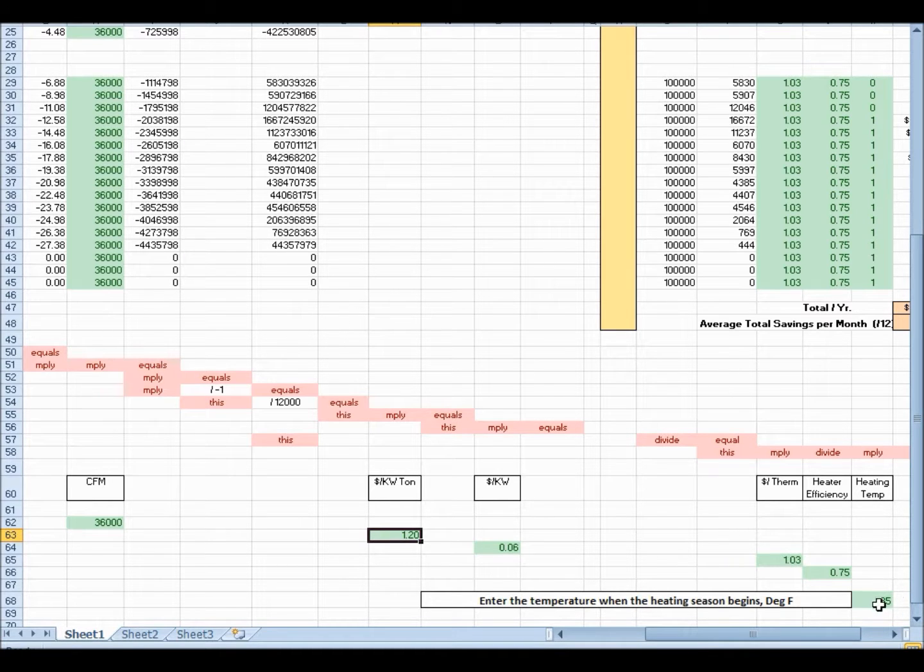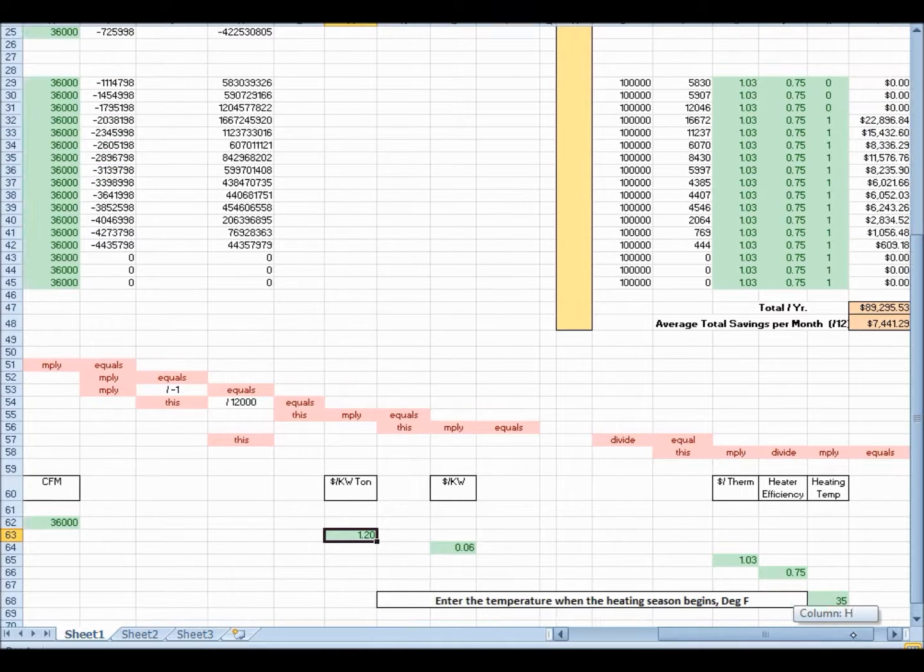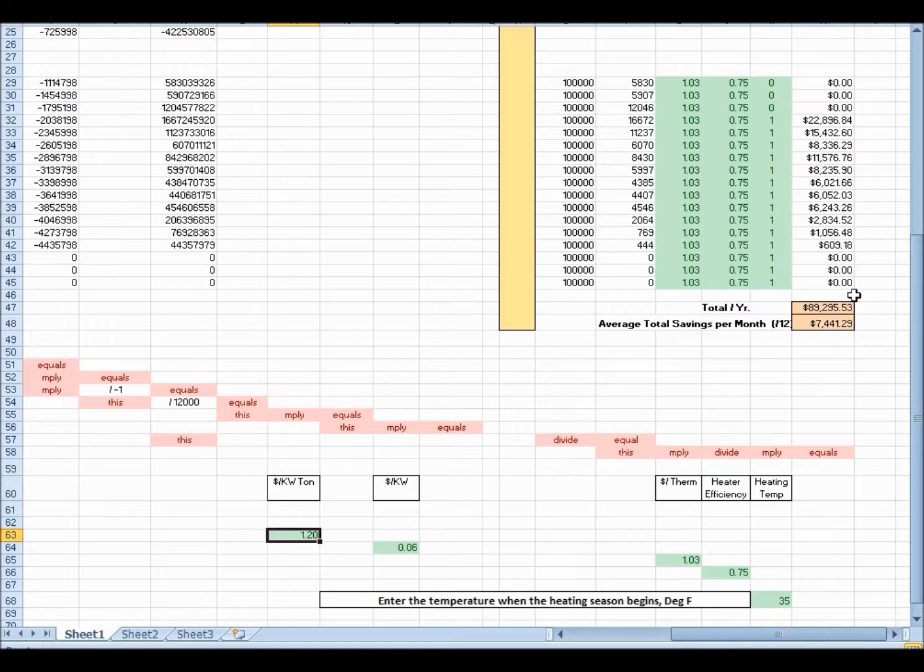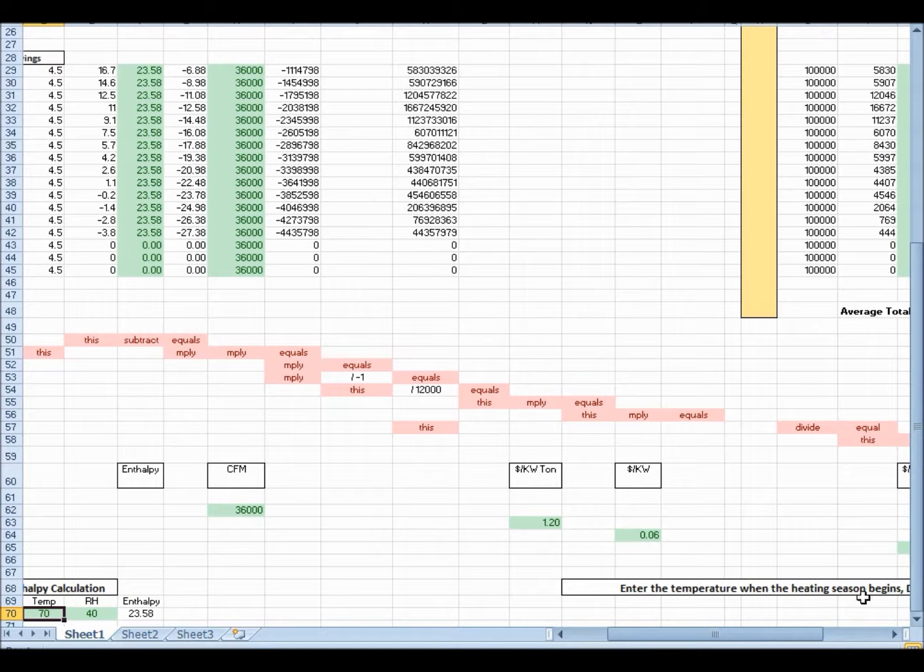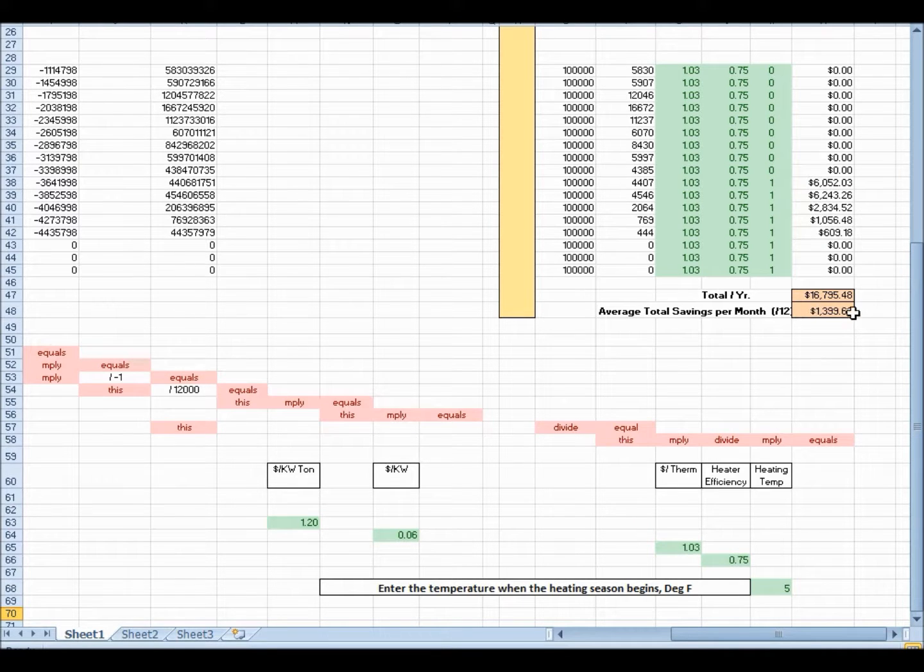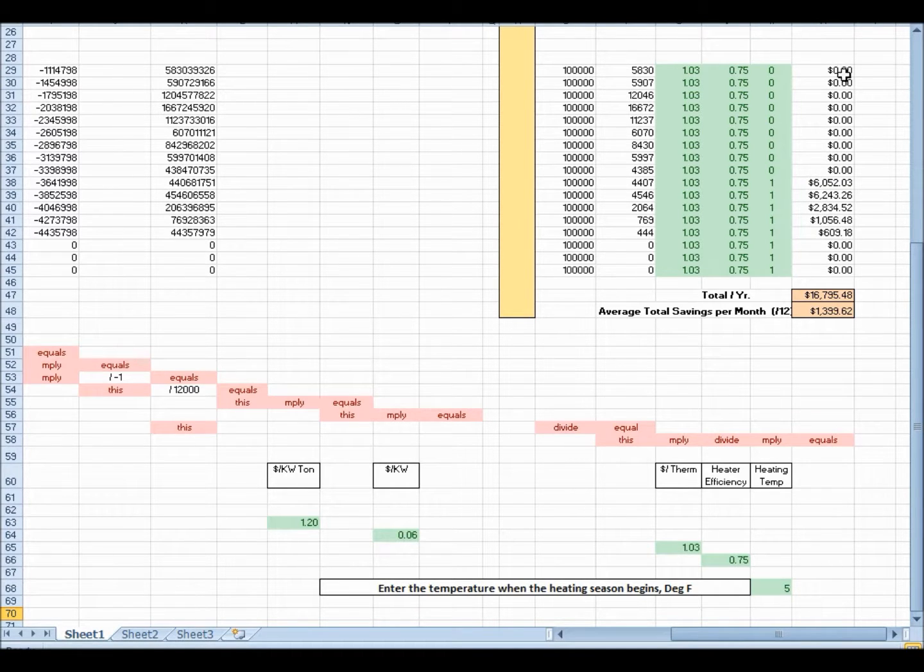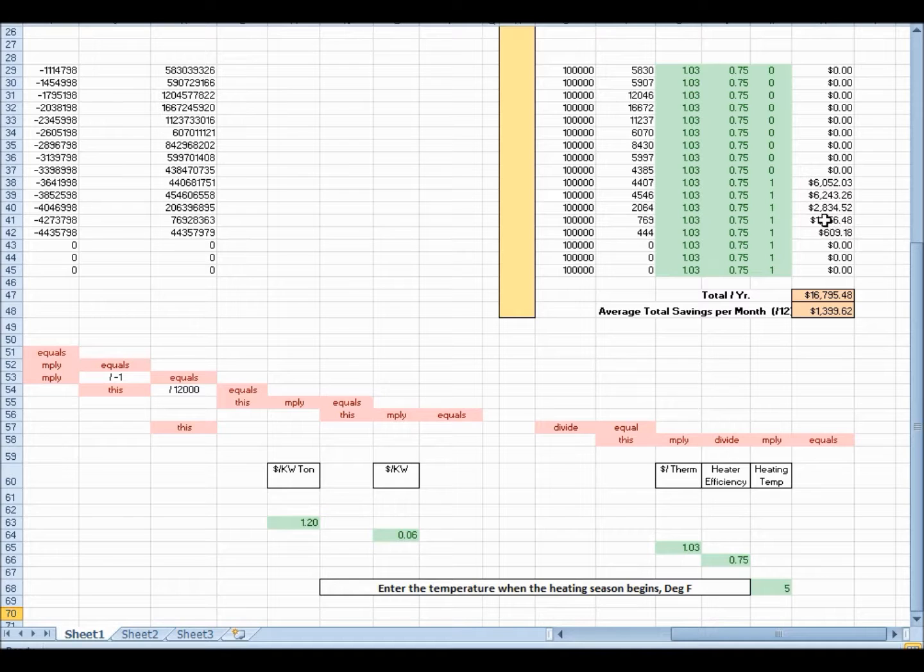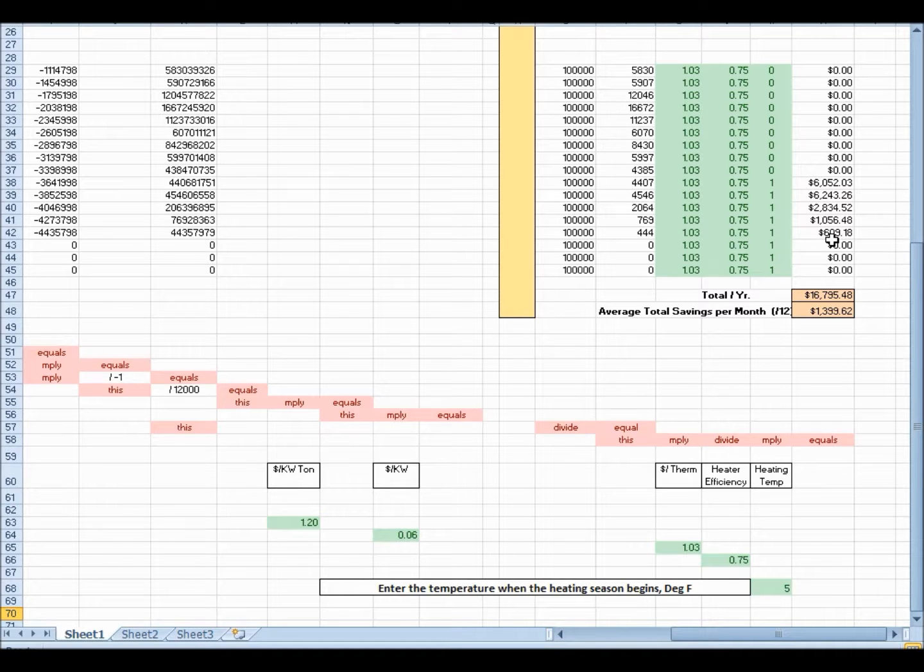So, what that's done is put zeros here, and then a bunch of ones, and those zeros here come out, so they're not added on to this total. So, let's change this once. Let's make this, well, it went into 5 degrees. Let's do 5 degrees. You can see that a lot more zeros came in here, and the savings is a lot less. This, all this area in here is where you're getting free cooling, and you're utilizing that cold air. Here's where the heating season starts, where you start to use natural gas for heating, and then here's where the energy savings calculations come into play.